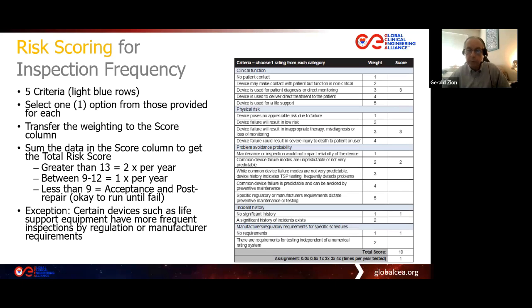But it was based on use hours about every 2,000 hours. And then every 10,000 hours, there was a different interval because you needed to tear down and do much more invasive testing and part replacement on the compressor. So that's just an example.